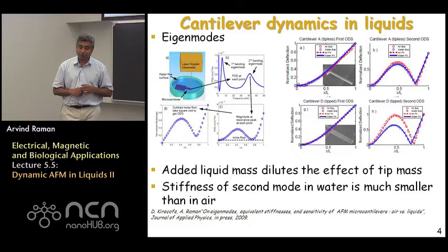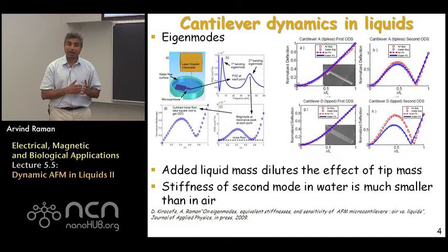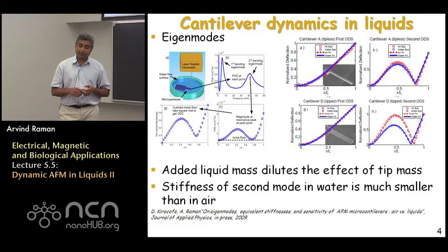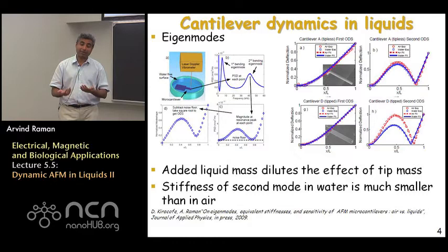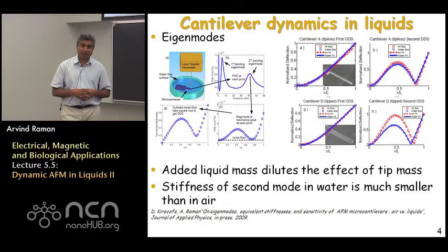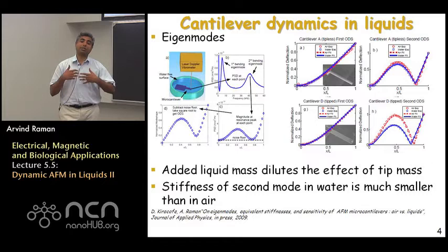On the other hand, for the second eigenmode — which is an advanced topic — there is a significant difference. Looking at the bottom right, for cantilevers with tips there is a notable difference in the vibration shape in the second eigenmode between air and water. The conclusion is that when dealing with higher eigenmodes, it is much better to perform stiffness calibration using thermal methods in liquid — in the medium in which you will be imaging — rather than assuming the air calibration constant applies. The key takeaway is that every hypothesis needs to be questioned and validated when doing dynamic AFM in liquids.